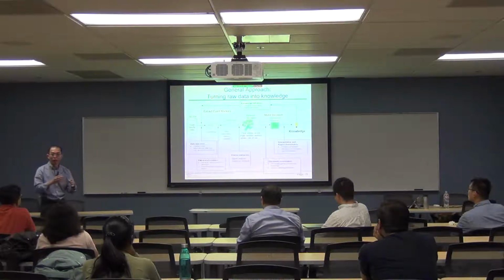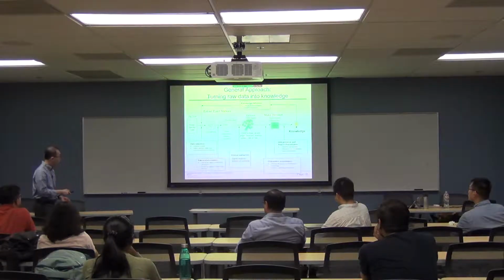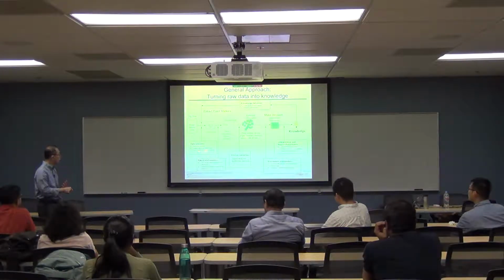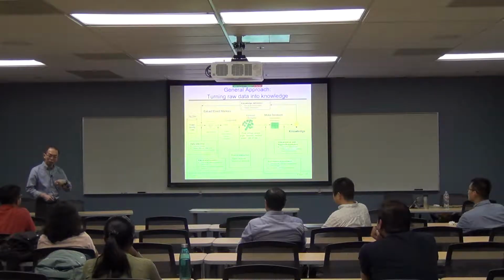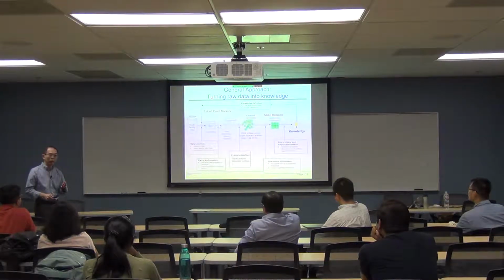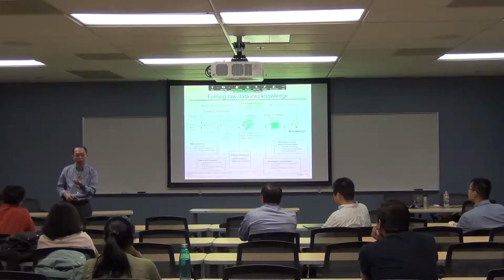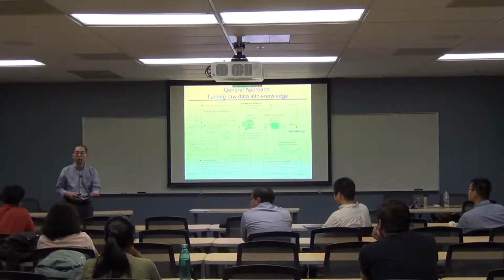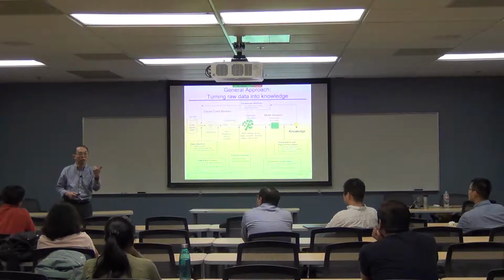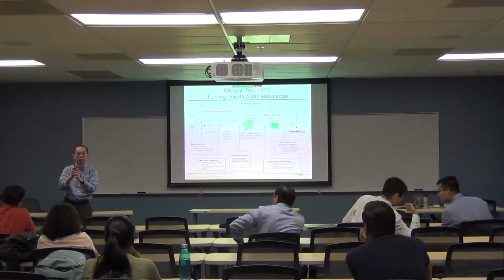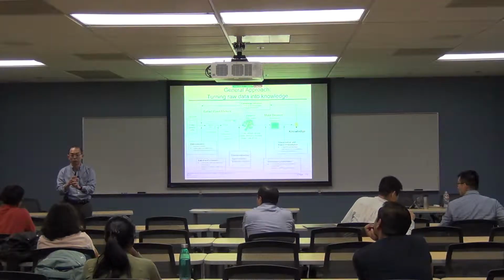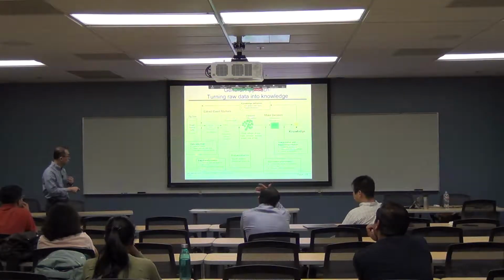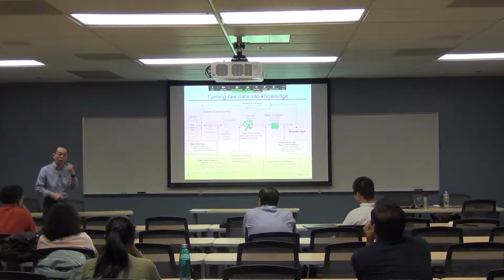This is like a very defensive type of algorithm development—you only want to select maybe waveform data and sometimes harmonics. The reason you need harmonics data is where system knowledge comes into play: when you energize a capacitor bank, it may move the system resonant condition closer to a point where it resonates with other circuits. So this could be the first successful step—if you choose the wrong data sets, your algorithm will have low performance.